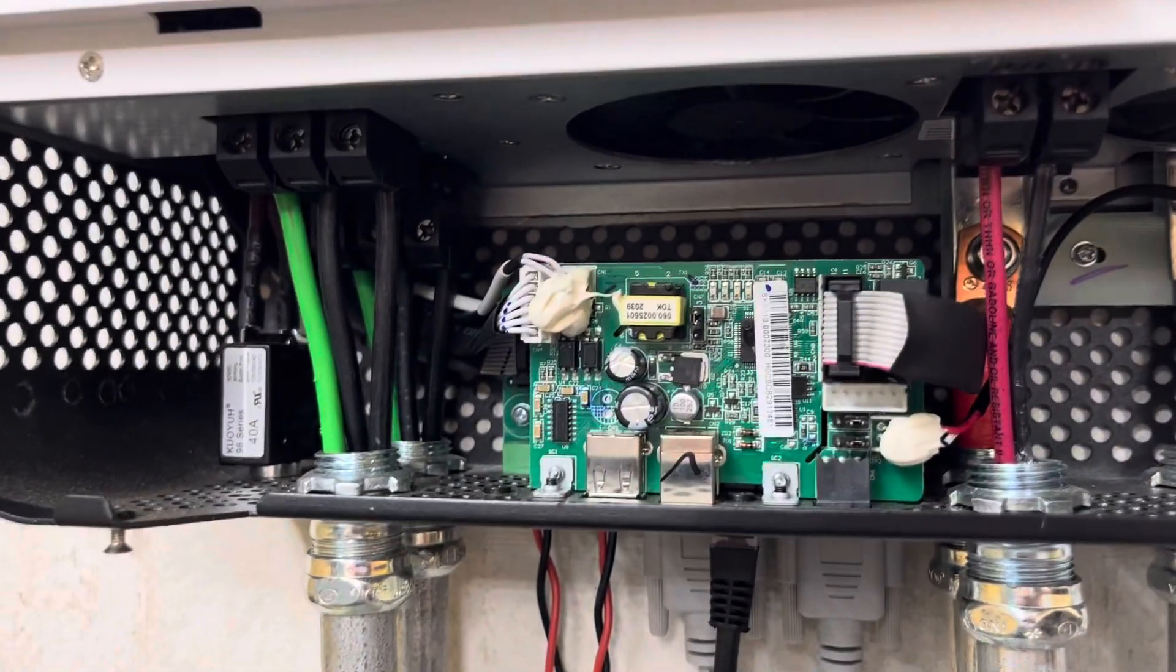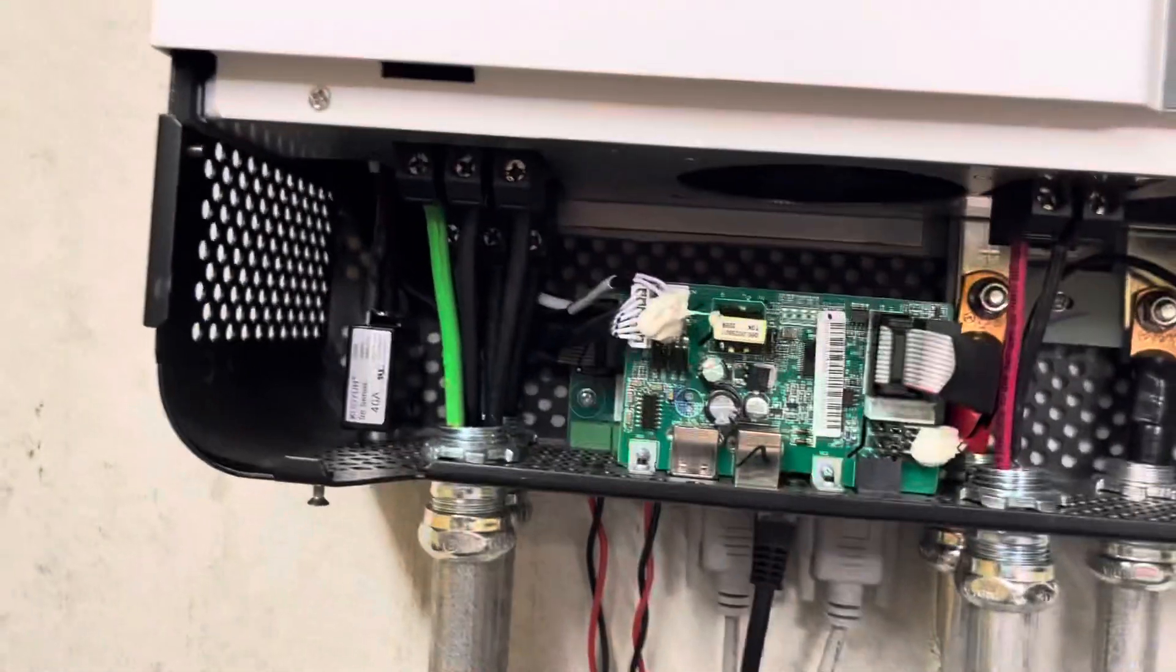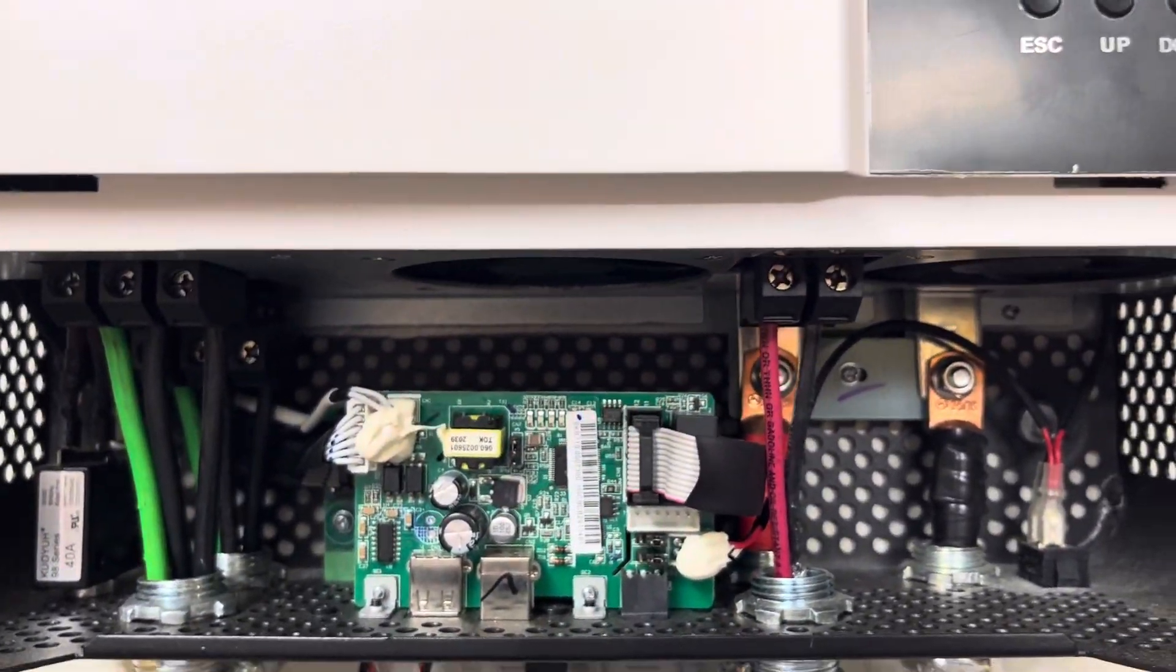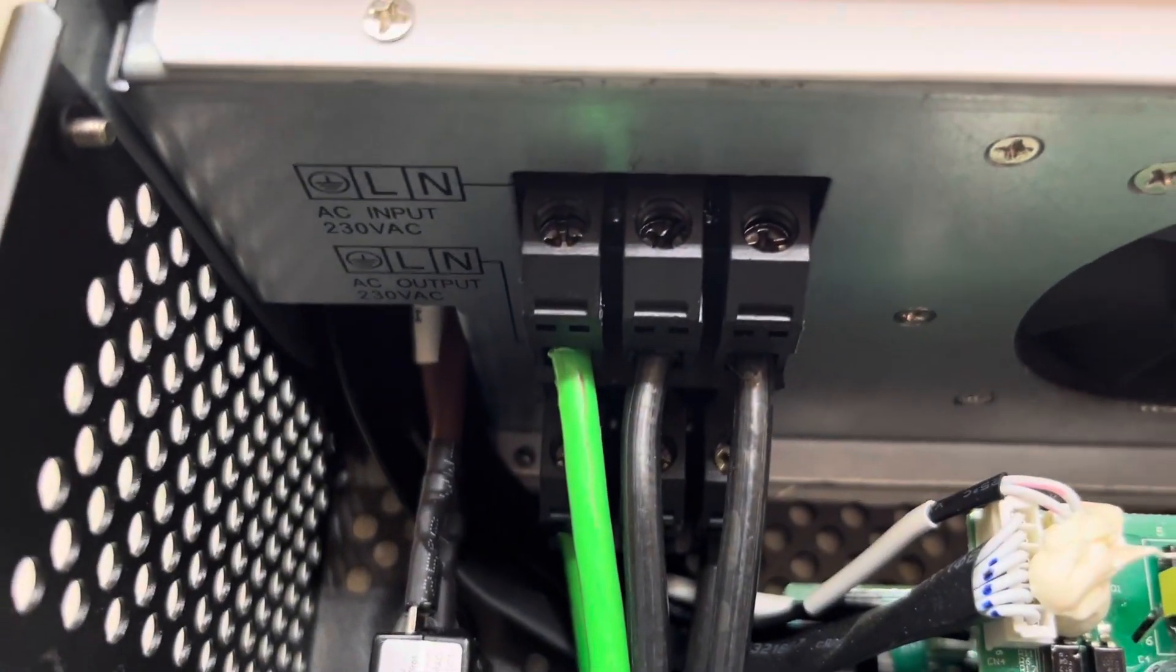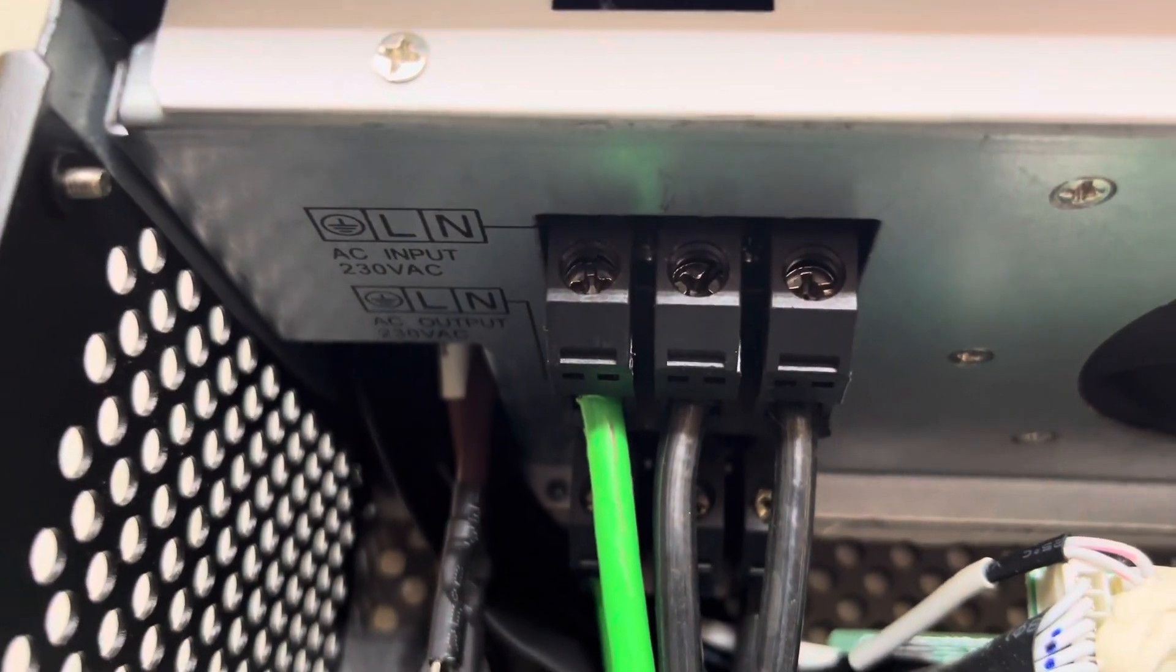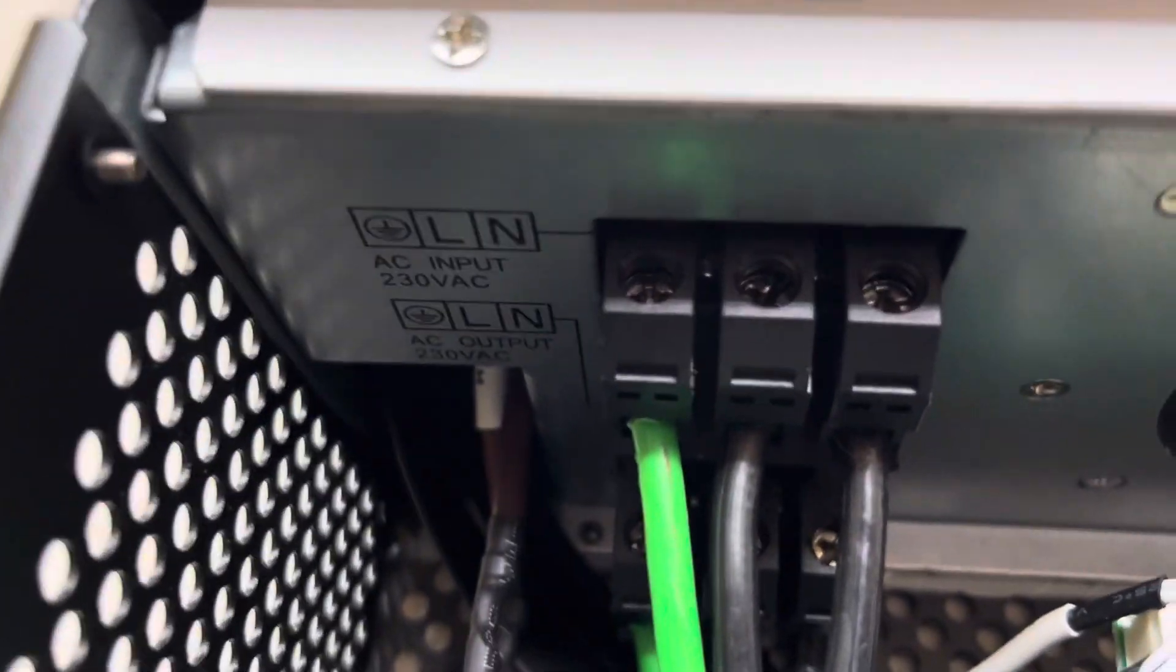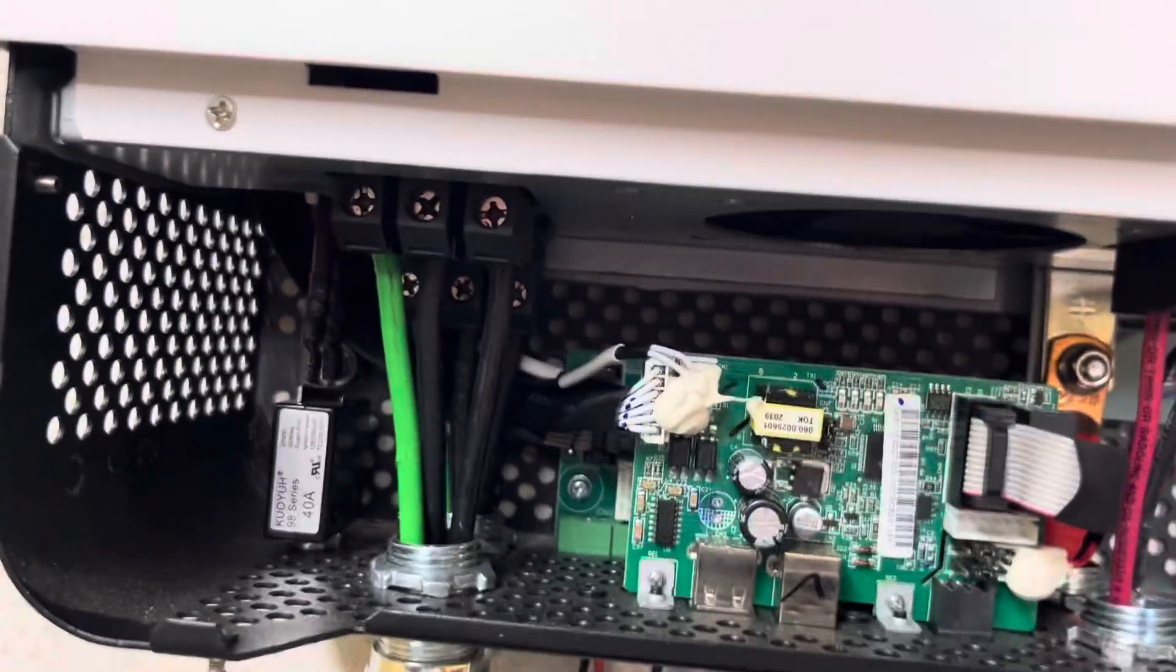Now, internationally, I think this is correct. I'm not an expert on international electrical standards. But in most of the countries around the world, they use 240 volts service with one of the legs grounded. So you have a grounded conductor in, which is what we would call L2, except our L2 is not grounded. They strictly have a two-wire service. In the United States, we have a three-wire service.